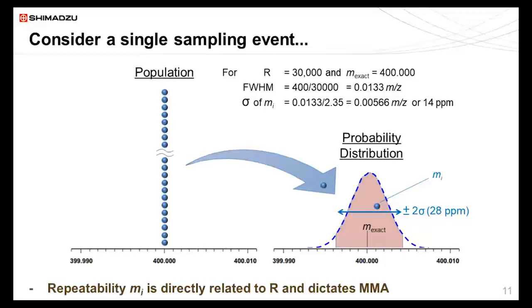Let's consider a single sampling event, a single sampling of an ion from the population of ions. Think of a mass resolution of 30,000 and an exact mass of 400. We could say that FWHM is 0.0133, and the expected standard deviation is 14 ppm. So we could deduce that for a single measurement, in 95% of the cases, the result will be somewhere around this 400 m/z, plus or minus 2 sigma, plus or minus 28 ppm. The repeatability of this measurement is directly related to resolution, and this dictates the mass measurement accuracy of a single ion.